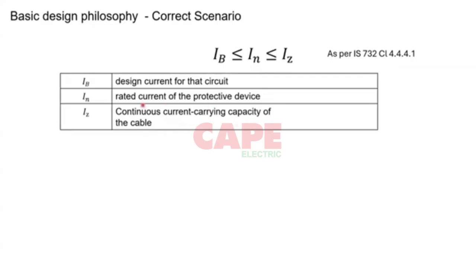This is after derating. So when you take these factors into consideration, rather than putting a load and then checking the cable size and then checking the protective device size, what we are supposed to do is first make sure the design current is correct. After that, you select the rating of the protective device. After selecting the rating of the protective device, you select the current carrying capacity of the cable, and then you check the voltage drop and all those other things. So from the load details you decide the rating of the protective device, and after that you check the cable sizes.